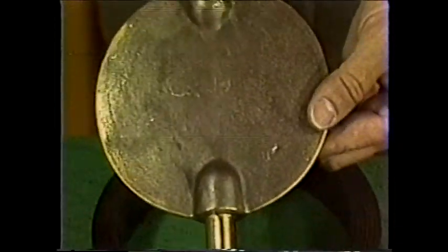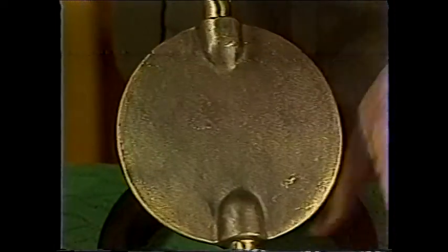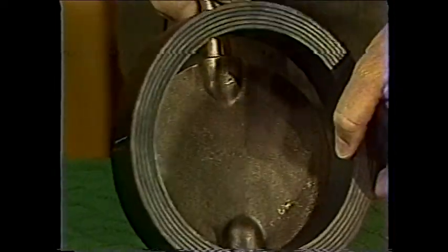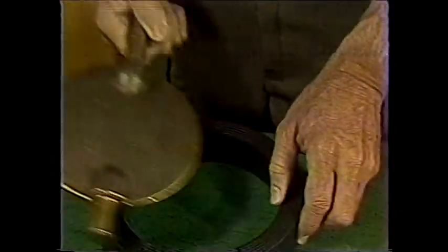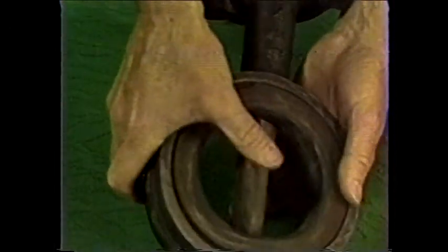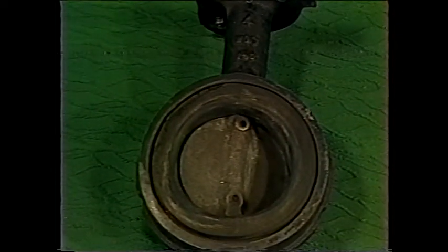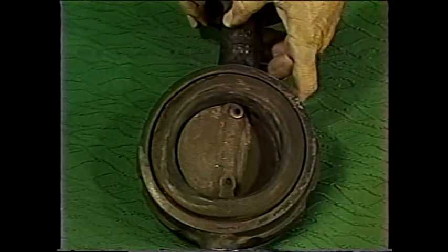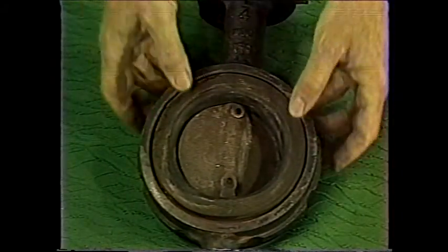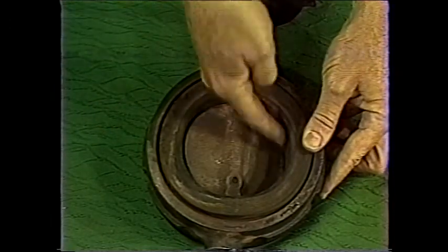Actually, they have a disc or butterfly like this, which is enclosed usually by a resilient ring. When it's turned like this, it closes the opening. Because of the simplicity of design, this valve is very economical in initial cost, but it normally is not used in applications which are operated frequently, since the wiping action of the butterfly as it closes causes relatively rapid wear.